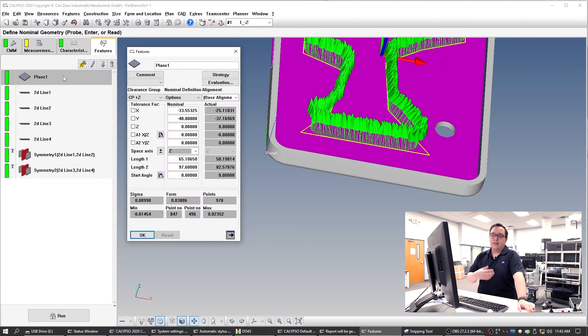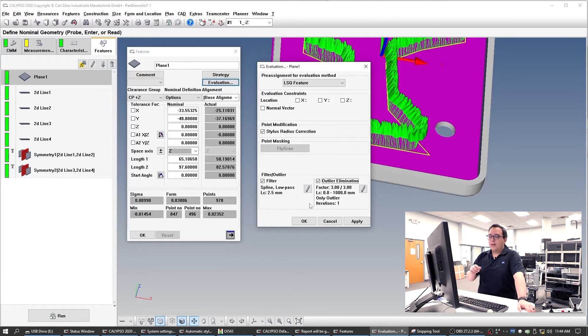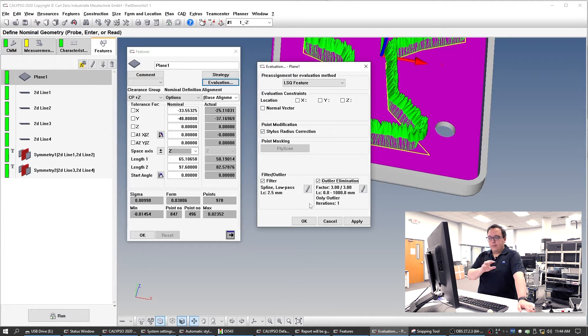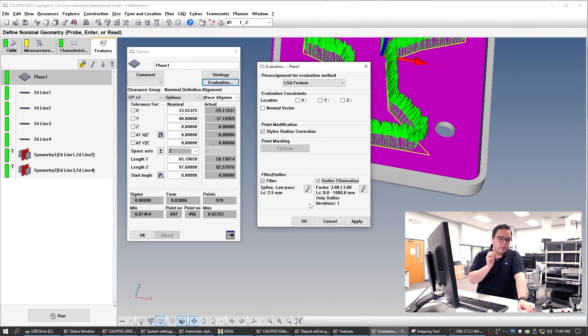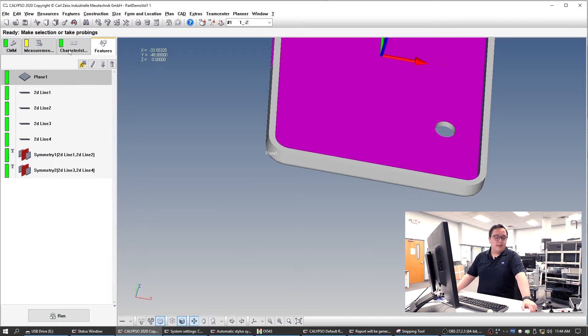Something else we can do is, because there's a feature we're going to be measuring, we should turn on some evaluation characteristics — these would be things like the filter and the outlier elimination. We have a cookbook that tells us exactly: if this is the size of the metal plane you're measuring, you should be doing this for a filter and this for an outlier. In general, 85% of the way there if you're just clicking these two things on. Now if you want to be very precise and you're working with microns, I would encourage you to look at the cookbook. And if you're a beginner, use the cookbook — it'll give you a sense of taste for what you should be expecting for the filter and outlier elimination.